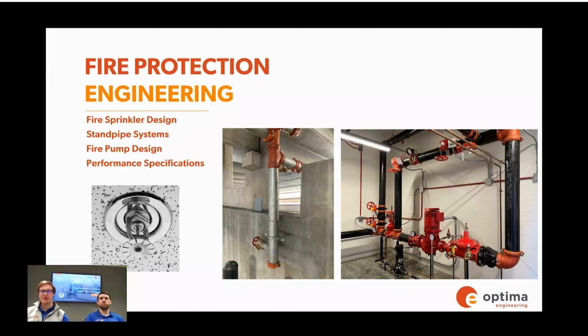You can see in the middle picture some specialty sprinkler systems designed for running piping inside unconditioned spaces like a parking garage. This is a dry pipe system where it's actually full of compressed air rather than water, but when a sprinkler head activates, the water rushes into the piping and gets to the sprinkler head so it can put the fire out.